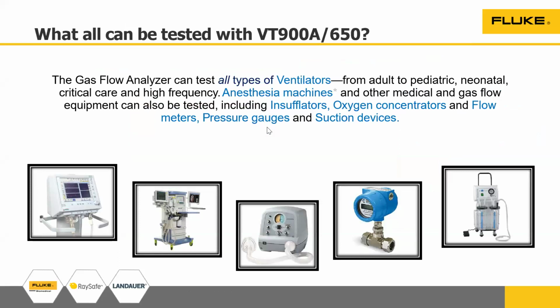Any gas flow products, there are gas flow analyzers available in the market with us also, and those kind of products can be used for testing. A ventilator or gas flow analyzer can be used for testing any kind of ventilator, anesthesia machines, anesthesia workstations, and products like insufflators and oxygen concentrators. You also have flow meters and various pressure gauges at various places inside the hospital. You can check all those things, and any kind of leakage you can identify much before it becomes an accident.